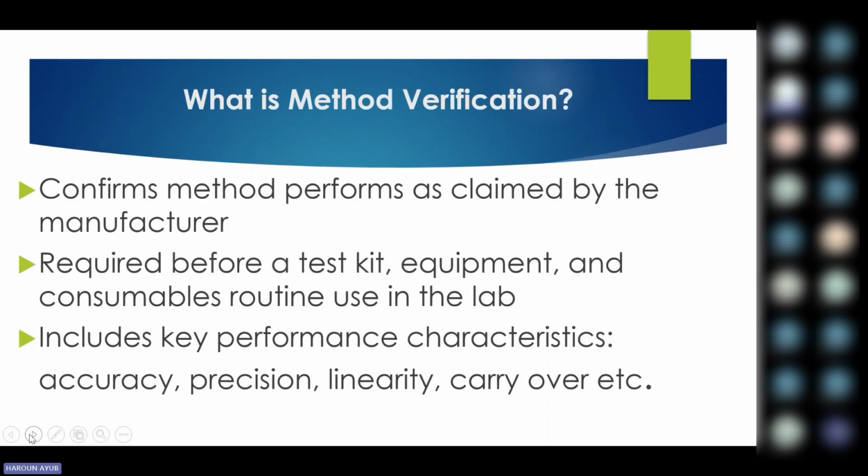And while running linearity, the first check the manufacturer will tell you is, do not run a patient sample in between these particular linearity studies. So you have 24 vials for hematology, and then you need to run each and every one of them 4 times. So let's say for hematology, you have WBC, platelets, RBC, HB, and HCT. If you are doing those 24 by 4 tests and you are only having one analyzer, you'll find the manufacturer has clearly stated, do not run any patient sample in between.